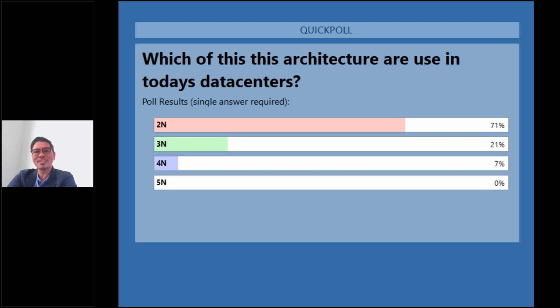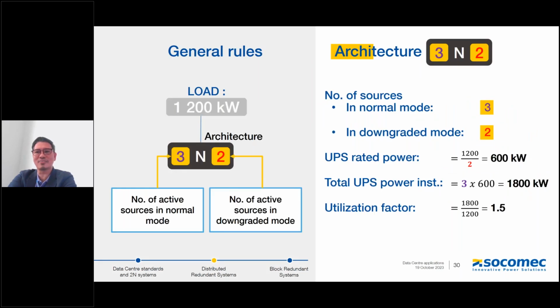That's why some architectures have gone into 3N2. They want to optimize it by using smaller UPSs, and they have more capitalizing, optimizing the solution. In this example, with the same load, we can use 3 units of 600 kilowatt, and we will have a utilization factor of 1.5, as we can see here.